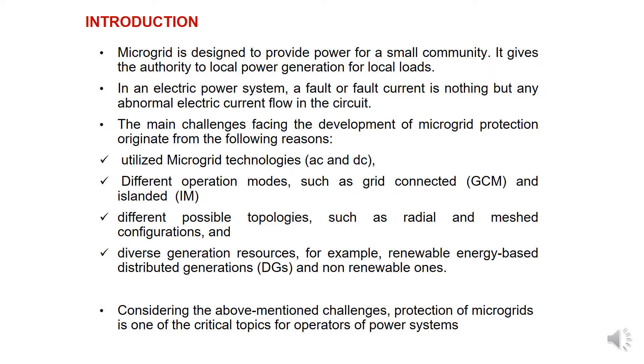Second, there are two types of operations in microgrid: islanded mode and grid-connected mode. Third, there are different possible topologies such as radial and meshed configurations. And last, it is also connected or integrated with distributed generations. These challenges are very critical topics for operation and protection of power systems, and it is very difficult to make a protection relay in microgrid.